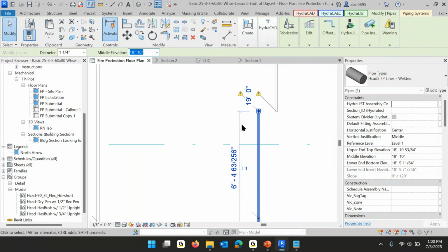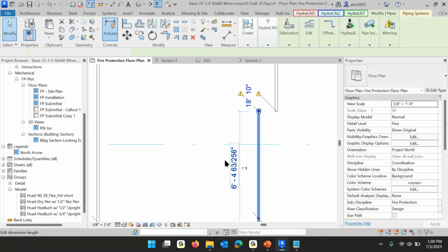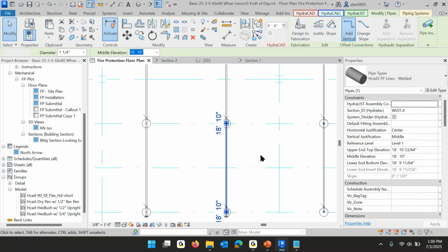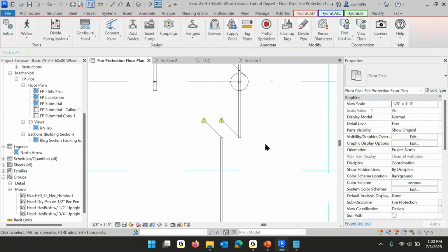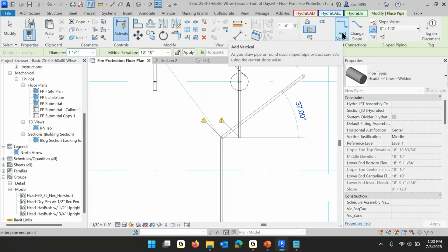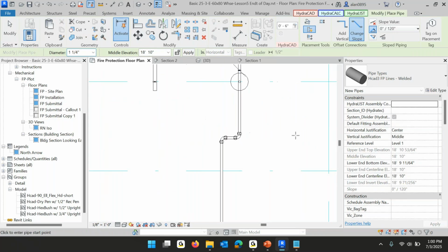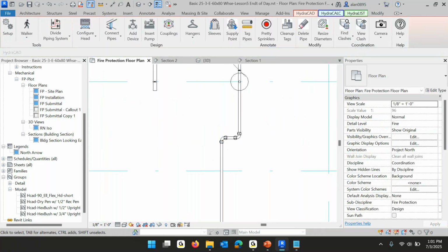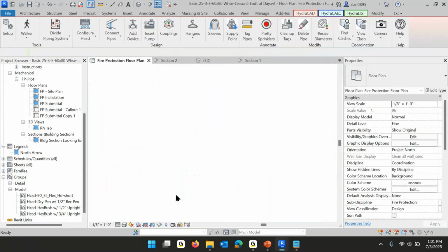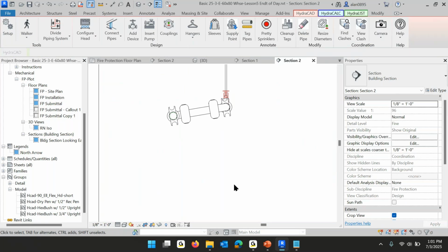I wanted 18 foot 10. And when I change this pipe to 18 foot 10, I changed this one and this one, right? But you can't get an elbow in there. That's only 2 inches. The trick is this: create similar, start here, but add vertical. That's going to try and go over and then go up 2 inches and say I can't do that. Change slope will put that in as a rolled elbow. Gotcha. Thank you.